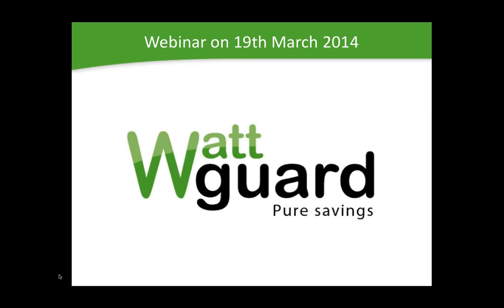Thank you, Mr. Christensen. We have another question. What does Wattguard effect do exactly? How does it help the electrode to launch electrons easily? What is the process behind it? That detail I cannot reveal, but I can say so much that the effect can actually be detected if you look at the electrode through a microscope. You will see that electrodes that have been run for only around 100 hours with normal tubes already have a surface that becomes uneven, and that's why they're starting to lose, already after 100 hours of operation, even up to 20% light effect. Some light units actually lose even more.